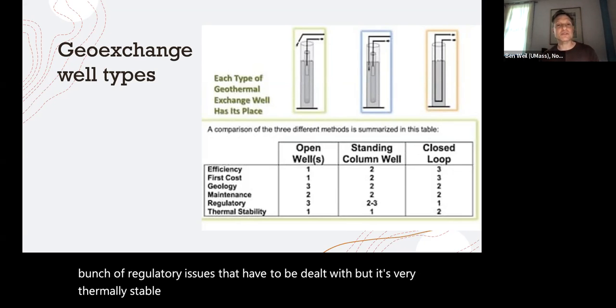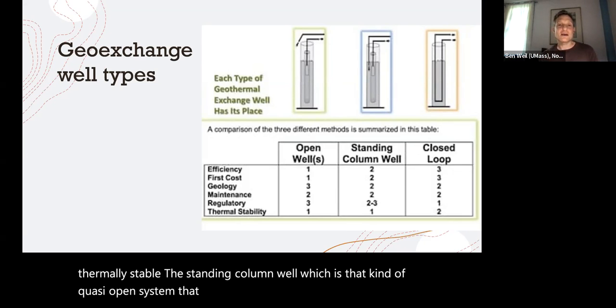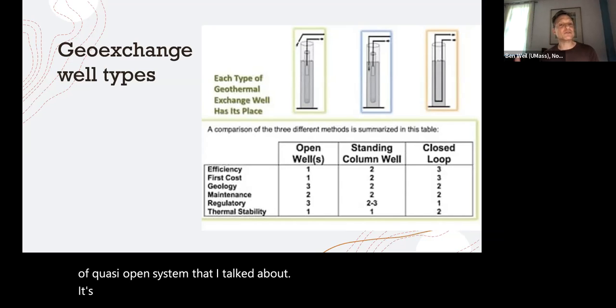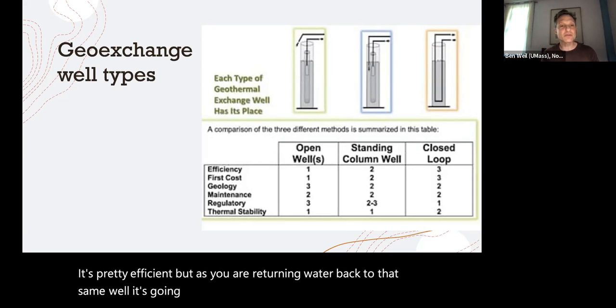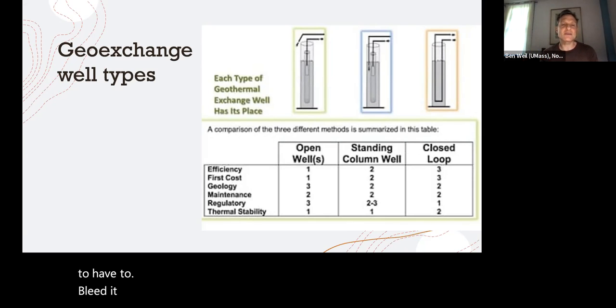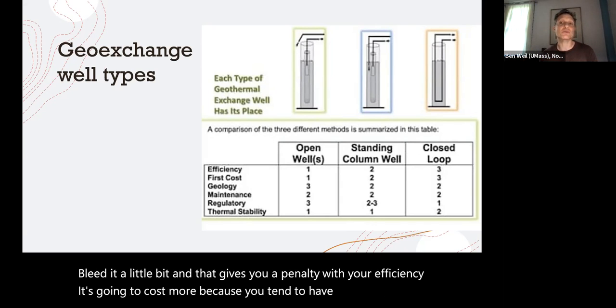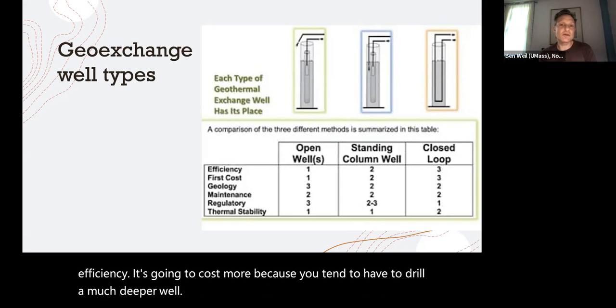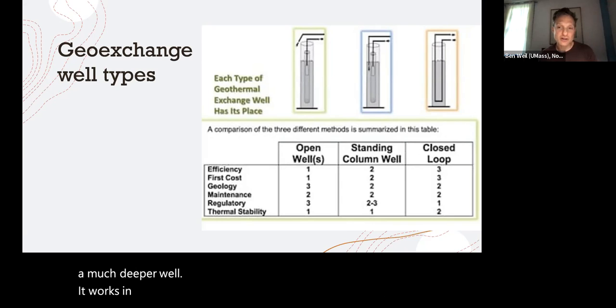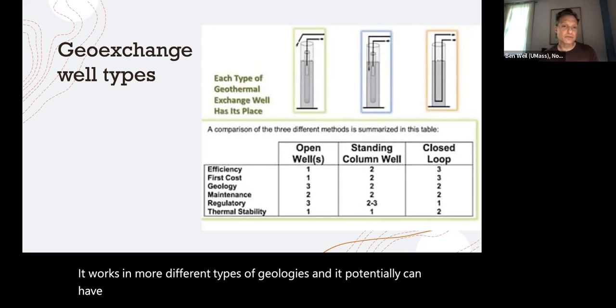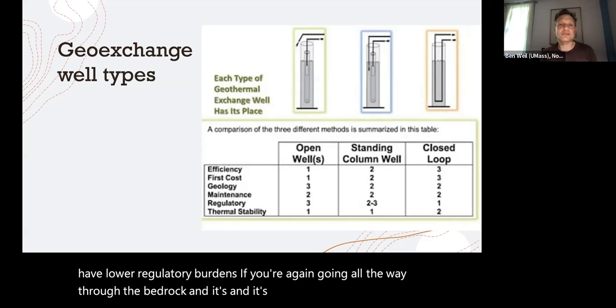The standing column well, which is that kind of quasi-open system that I talked about, is pretty efficient, but as you are returning water back to that same well, it's going to cool down a bit. And so now you're going to have to bleed it a little bit, and that gives you a penalty with your efficiency. It's going to cost more because you tend to have to drill a much deeper well. It works in more different types of geologies, and it potentially can have lower regulatory burdens if you're again going all the way through the bedrock, if the geology is just right, basically.